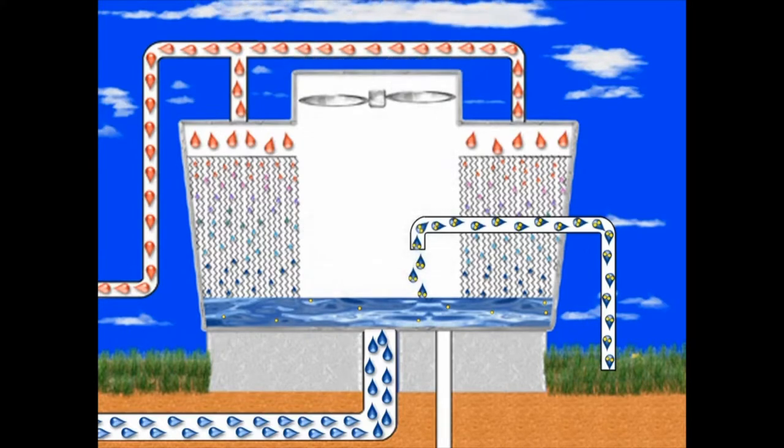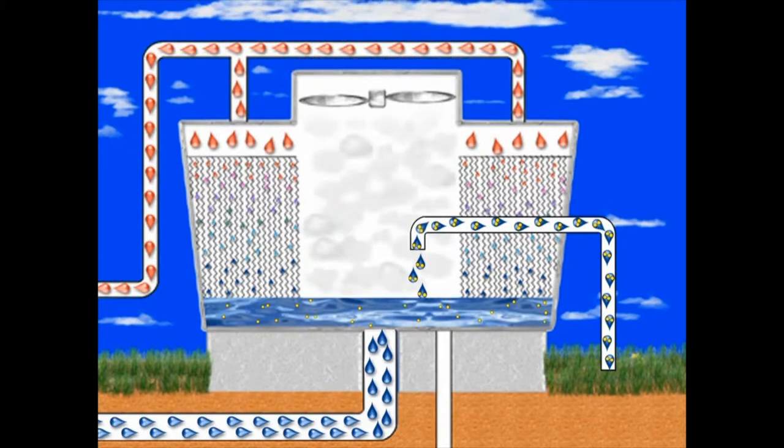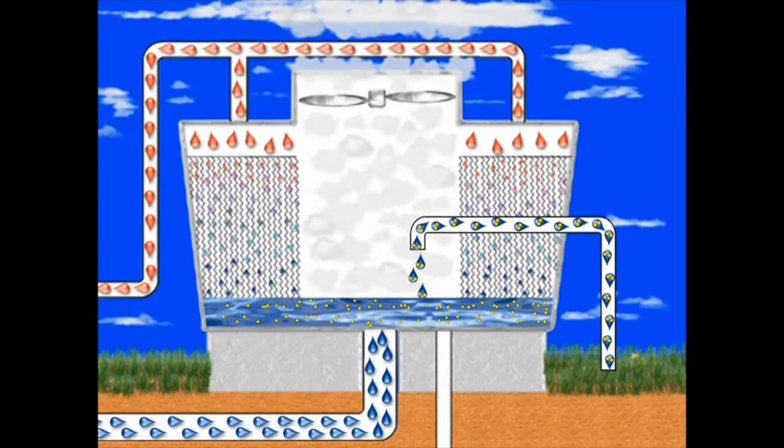This fresh make-up water carries additional elements into the system water where they accumulate. The more water that evaporates, the greater the need for make-up water to replenish the system and the faster the concentration of elements build.